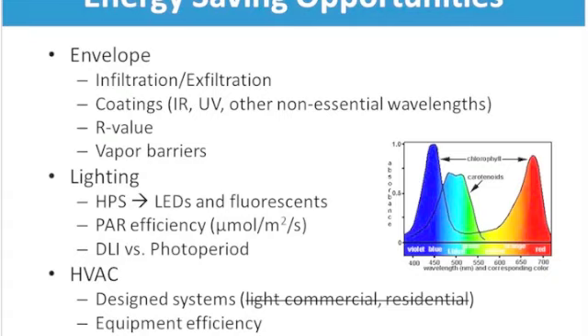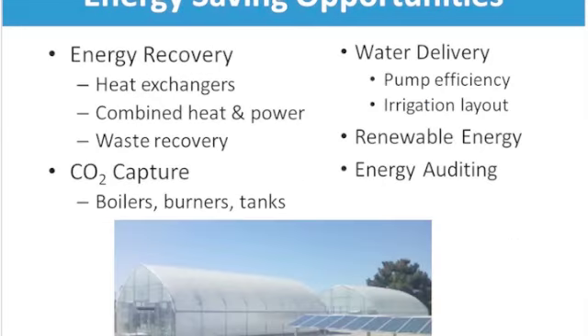If the outside air is the right temperature and humidity, you could bring in 100% outside air to condition your room without using air conditioning at all. It's a huge savings if you don't have to turn on the compressors and just use the fan to blow air. But if you choose the economizer route, make sure it has dew point control. If it's just temperature control, you might not be managing your humidity, even if you're managing temperature.